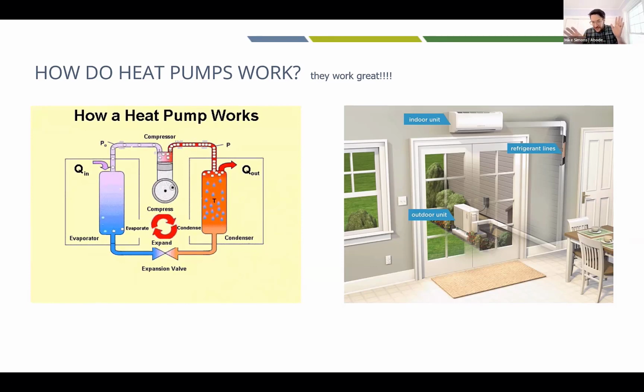It may not seem like there's a lot of energy in 0 degree air, but 0 degree air is a lot warmer than -30 degree air. So we have -30 degree refrigerant and 0-degree air. That refrigerant over time is going to become 0-degree refrigerant. How that happens: there's a fan on this system blowing 0-degree air over this -30 degree refrigerant that's inside of a coil.